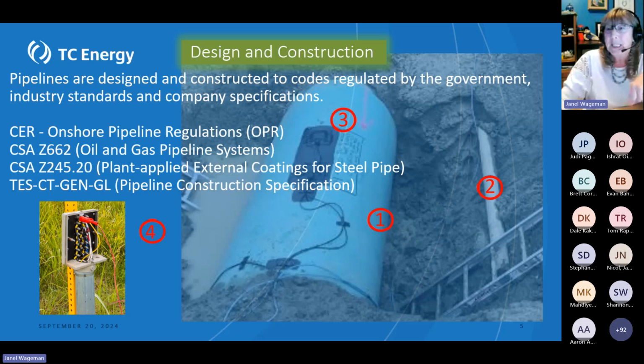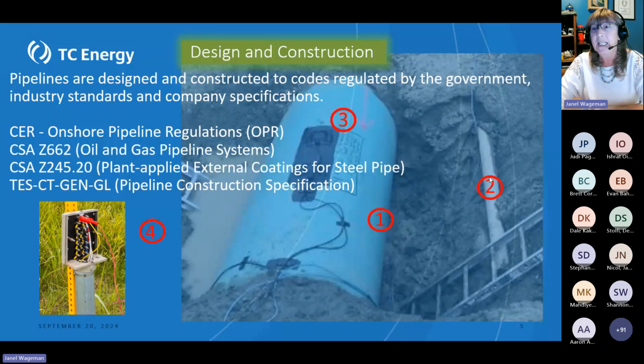Number 2 is indicating what's called an anode, a sacrificial anode. It's about maybe 2 meters long. It looks like it's longer, but it's kind of cut off just where the dirt is on either side. It's made of a material that corrodes faster than the steel, so it could be made of zinc or magnesium. These two metals are bonded together electrically with cables, and they create an electrochemical situation. So by having the zinc anode deteriorate faster, it in effect saves the pipe.